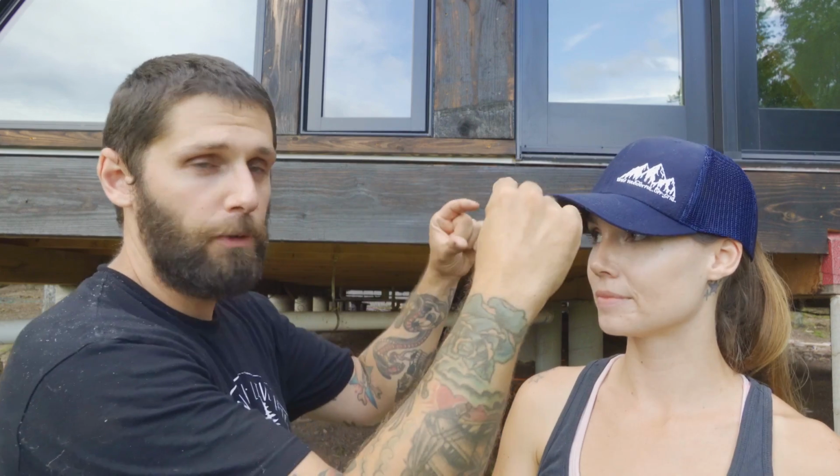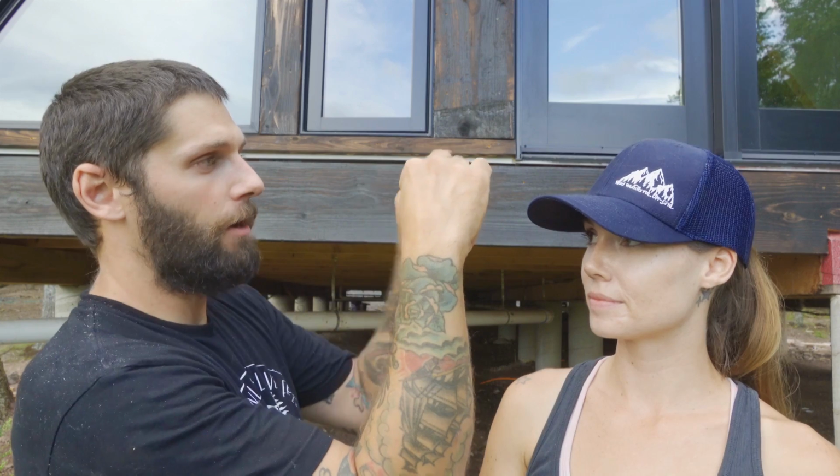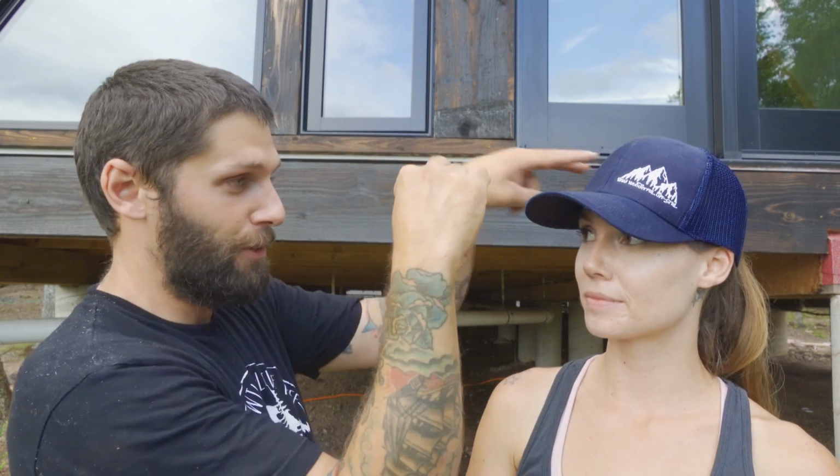We got a good start on half of the house, this side of the house. Done. We're putting up 1x2s. We're slamming them tight to the subfloor. The reason behind all this is we're going to run radiant piping through. That's going to attach to the subfloor also with aluminum transfer plates, and those are going to staple to the bottom of the floor. The 1x2s go to the subfloor like that, and then our radiant piping is going to go through that way, and then we need a 2-inch air gap.